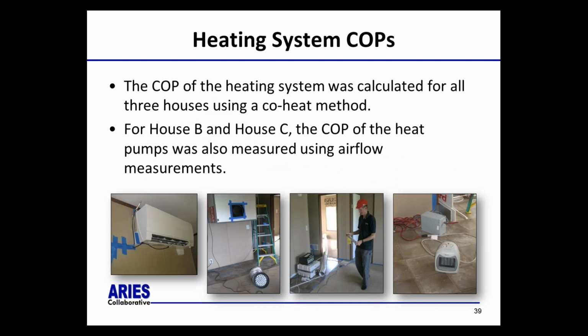So this was an interesting component of the work. We wanted to quantify the coefficient of performance for heating of the heat pump, and we measured it in two ways. We used a co-heat method, which you see in the photos on the right, in concert with tracer gas measurements and electric resistance heating, and then with an airside airflow measurement. So looking at the inputs and outputs of the heat pump in terms of temperature and moisture, relative humidity, as well as doing a flow map of the heat pump, so we knew we could predict what the performance was at any given time during the monitoring period.